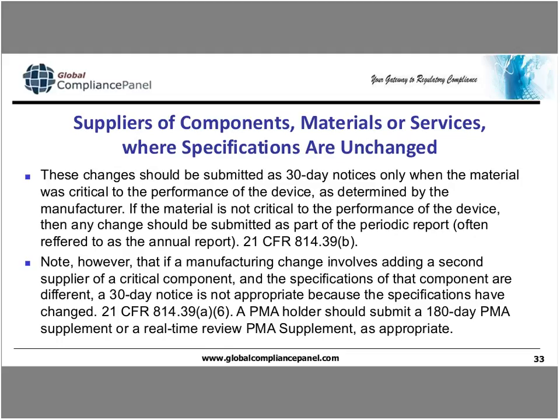Suppliers of components, materials, or services where specifications are unchanged. These changes should be submitted as 30-day notices only when the material was critical to the performance of the device, as determined by the manufacturer. If the material is not critical to the performance of the device, then any change should be submitted as part of the periodic report, often referred to as the annual report.